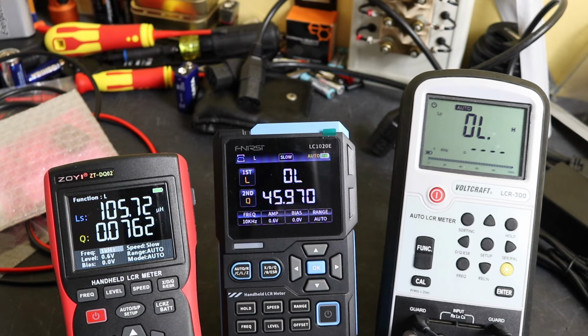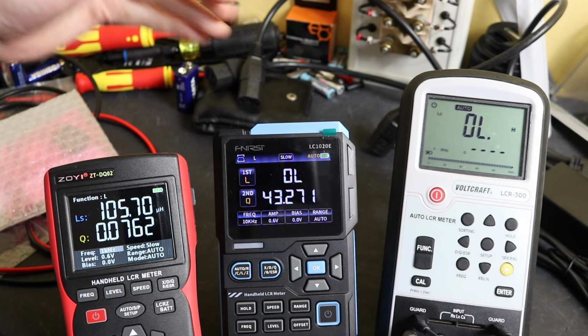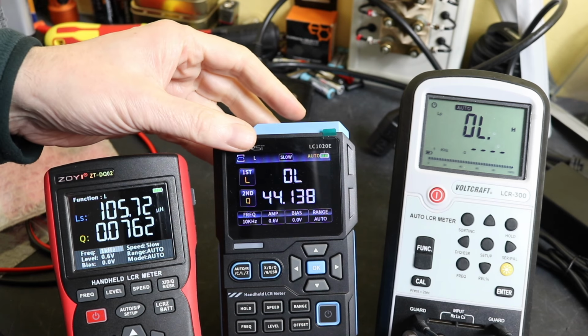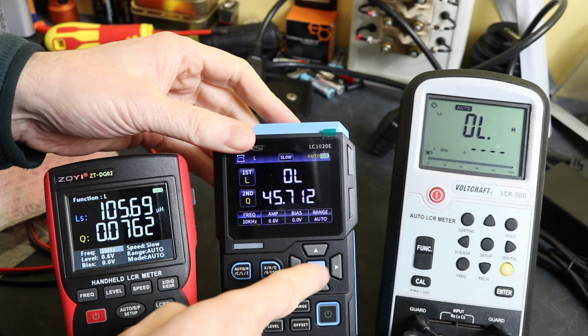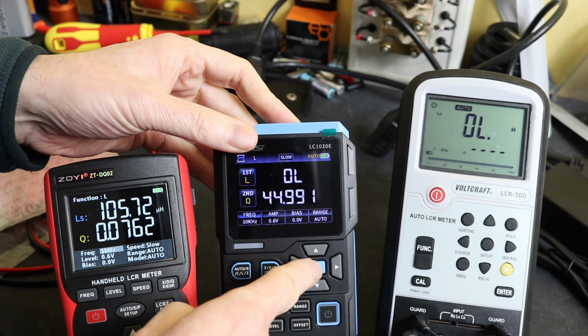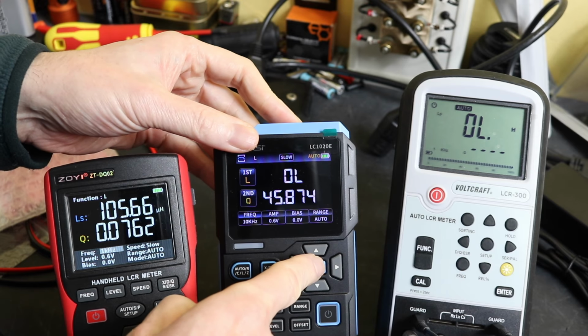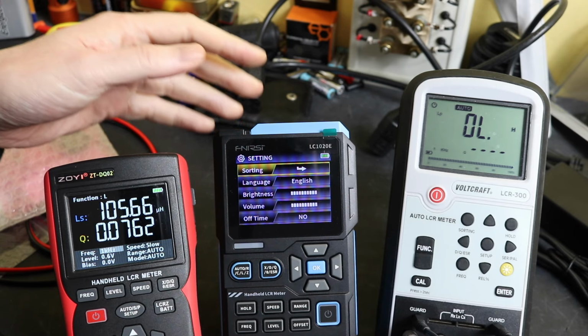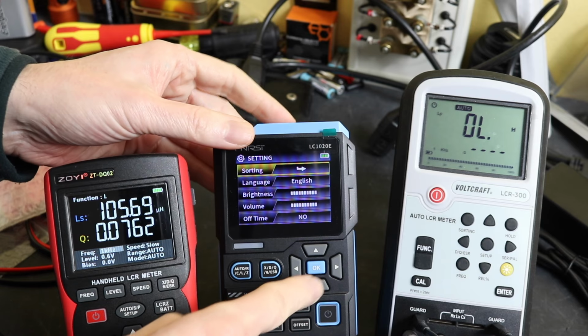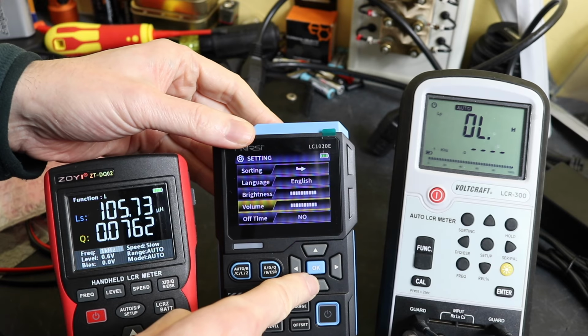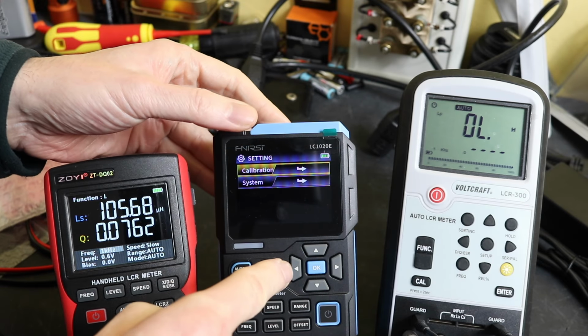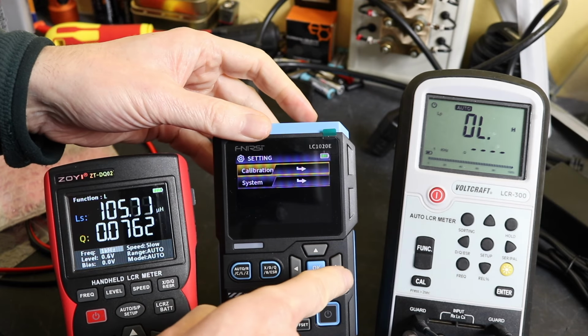Now the other thing that was suggested was a calibration on these units. Generally speaking, I find that the calibration for inductance measurement doesn't make a vast amount of difference. There's a reason for that, because although they call it a calibration, it's a little bit cheeky. It's not a calibration. What you're doing is you are zeroing the leads for resistance measurement and taking out the capacitive reactance. So unless you have a particular inductor with a very low resistance, or you hit some strange resonance issue between the capacitance of the leads and the inductor that you're testing, it doesn't really affect an awful lot.